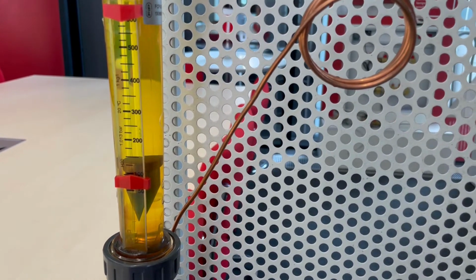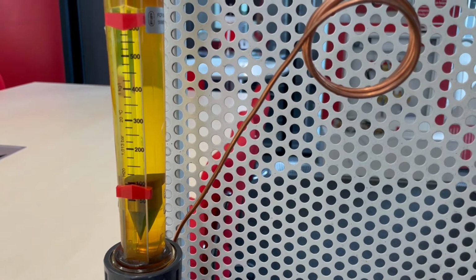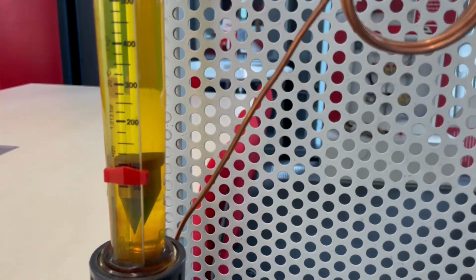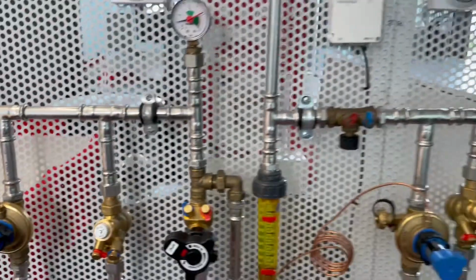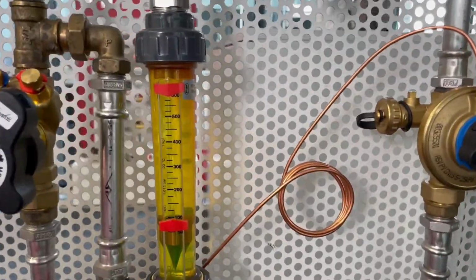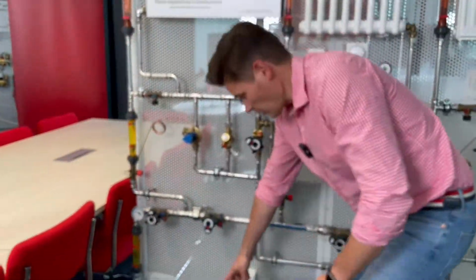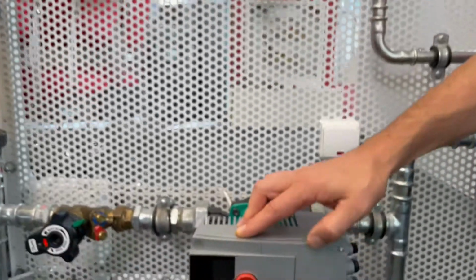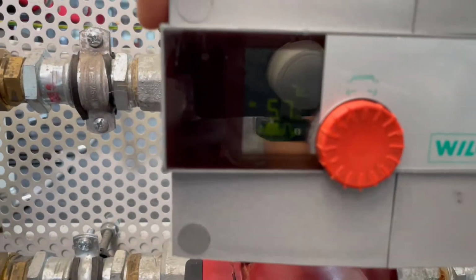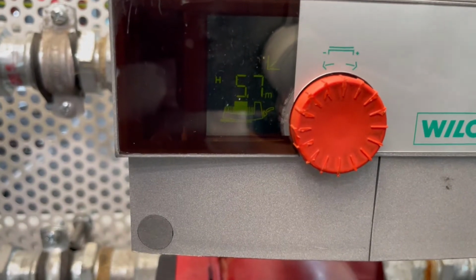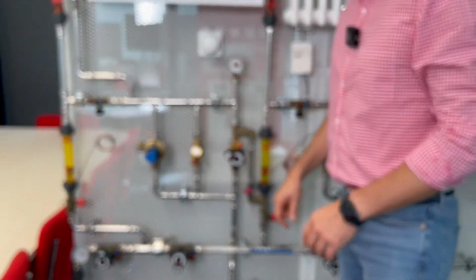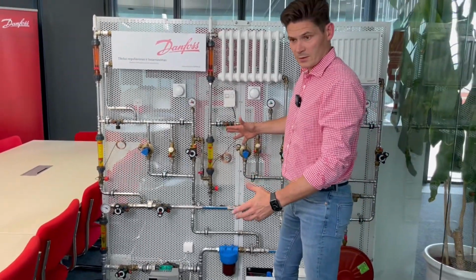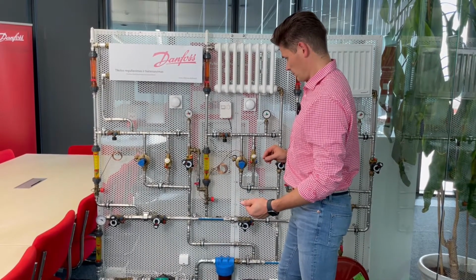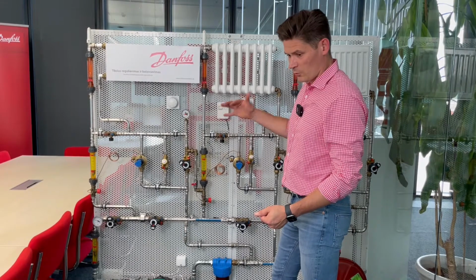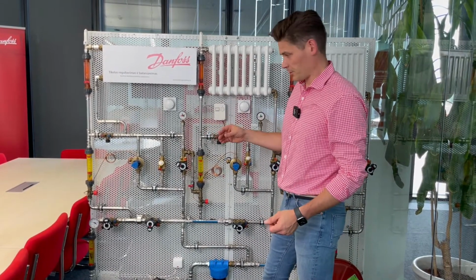Okay. Or maybe too much. Maybe too much. Okay, 100 liters. But not everywhere. 100. I go back to the last riser. Okay, and the setting of the pump is 5.7 meters. So now the pump head is optimized, and our system is balanced at full load, and also at partial load.